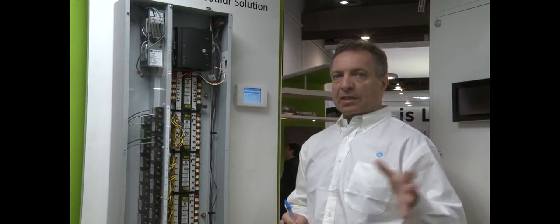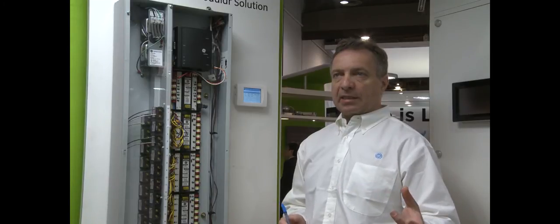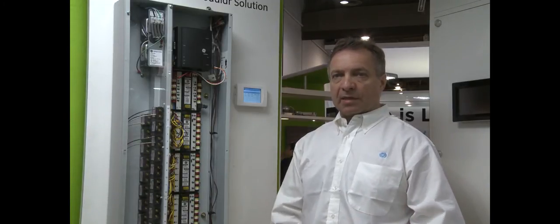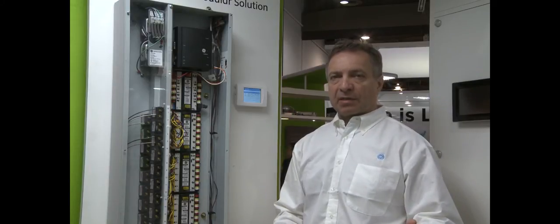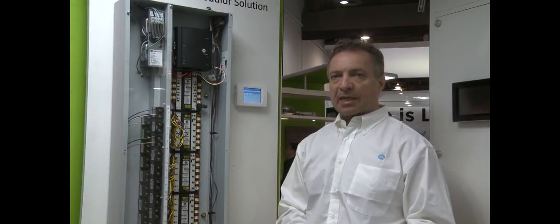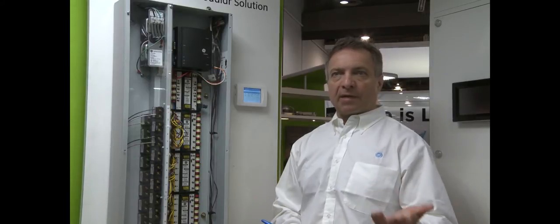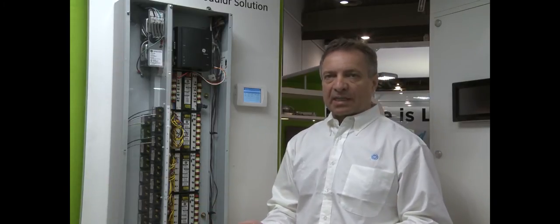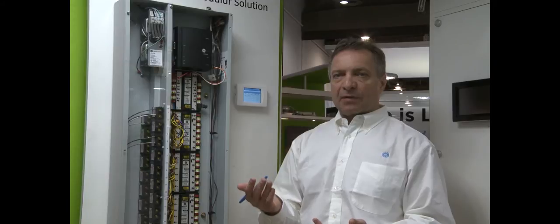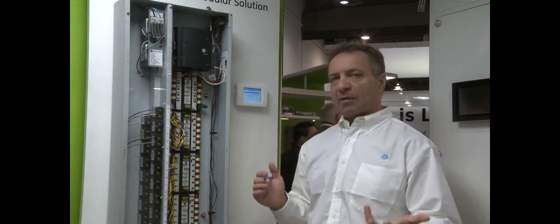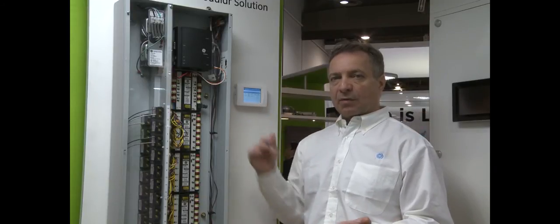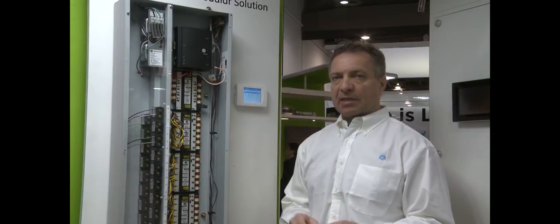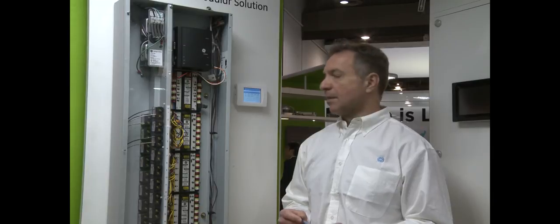If I have the photocell installed into an interior office, it's very important the surface below the photocells. So a bright surface is going to reflect more light, a darker surface is going to reflect less light. But we would like to create in that office to maintain, let's say, for example, a 35-foot candle. So it's important that we can calibrate that photocell to read closer to that value. So the system allows to do a calibration. We can come with a light meter. We see the reading of the photocell. We can input the readings from the meter and the system automatically is going to calibrate to show the right reading.